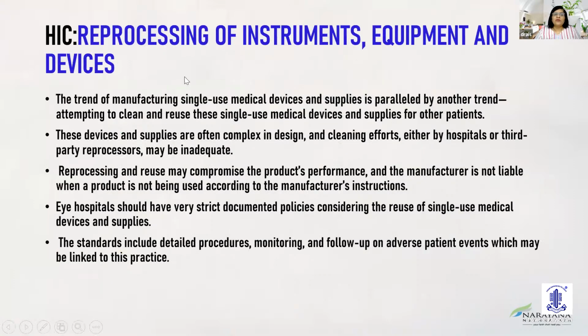Okay, now coming to the next one, which is the reprocessing of instruments, equipment and devices. Now what happens is that we use single-use medical devices, and the supply of these is paralleled by another trend, which is attempting to clean and reuse these single-use devices and medical supplies. These devices are often complex in design, and cleaning efforts by hospitals or third-party processors may be inadequate.